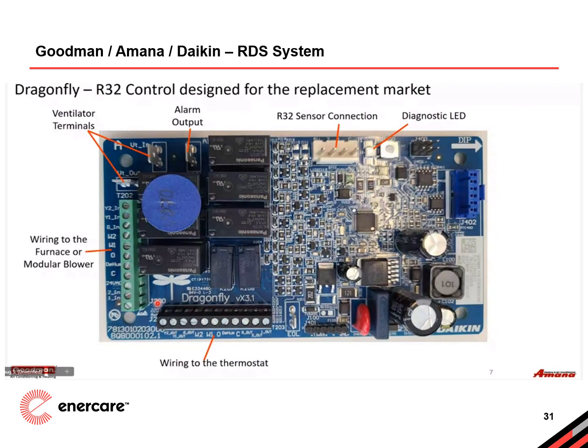The Daikin RDS system follows a similar strategy and is designed to be paired with a non-A2L furnace or air handler. The Dragonfly control pictured, like the previous manufacturer, also provides terminals for the appliances, RDS sensor, rated for R32 in this case, and the thermostat conductors. This one does, however, offer an alarm output to power a field-provided and installed alarm, and has an integrated diagnostic LED and push button.